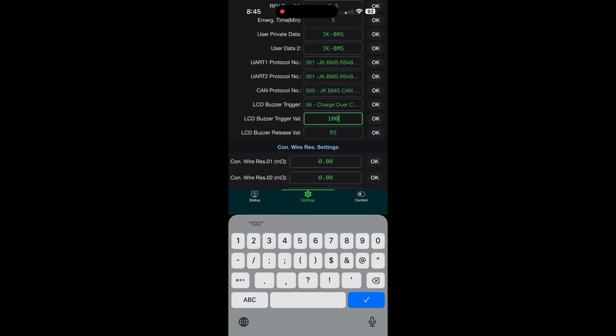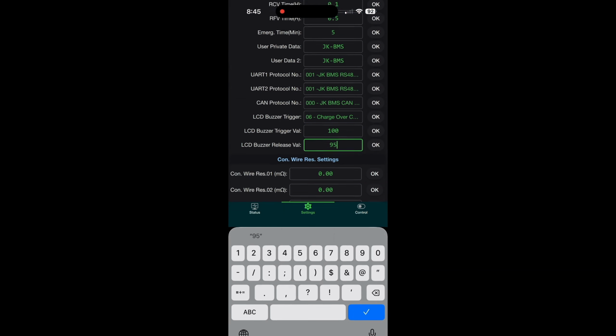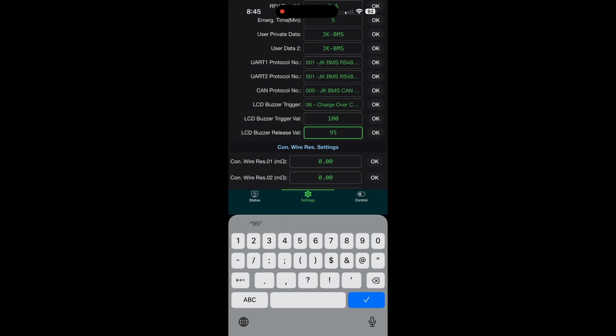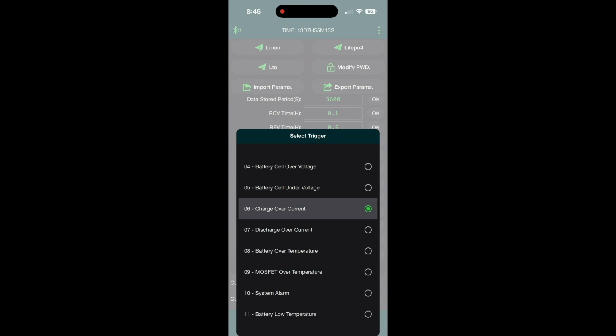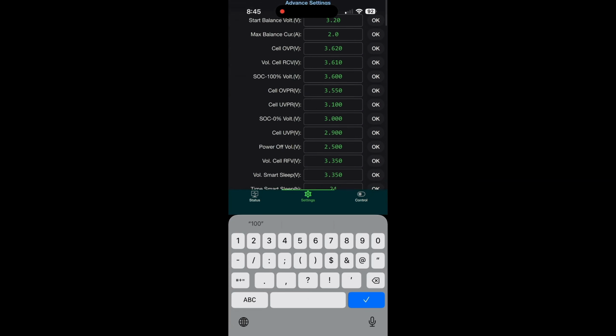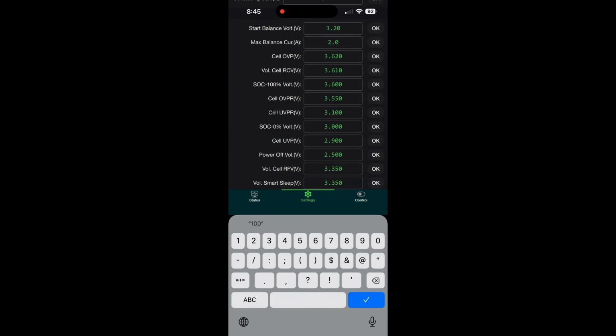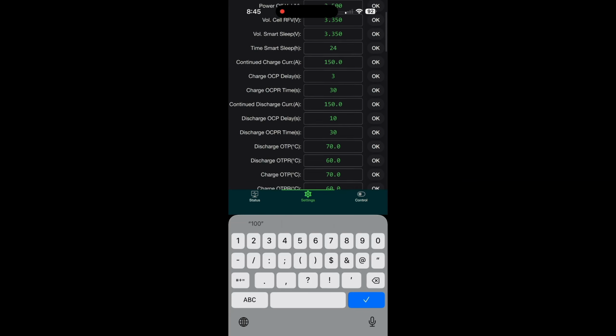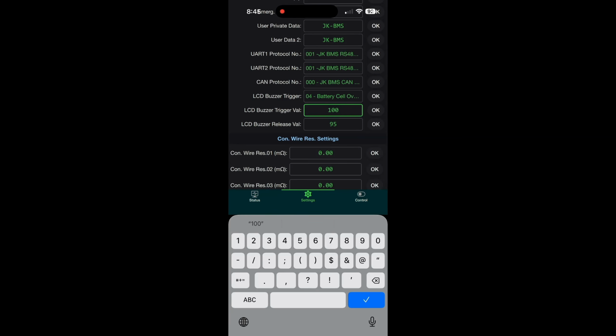The next one down is the LCD buzzer release value - when do you want the buzzer to release? At the moment it's 95%, meaning that once the value which triggered the alarm drops below 95%, the alarm will turn off. So if you've got cell over voltage as the setting, and cell over voltage protection is set to 3.62, then when it reaches 100% of that value, the alarm will go off. When it gets to 95% of that value, that's when the alarm will stop. So that's basically those two settings there.